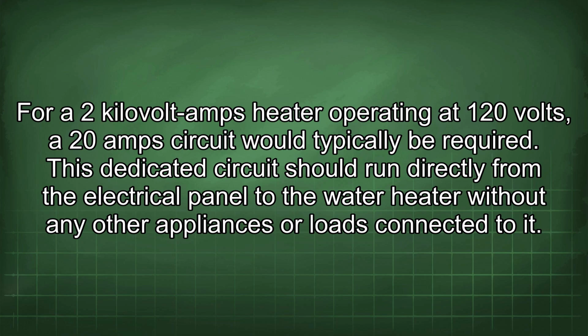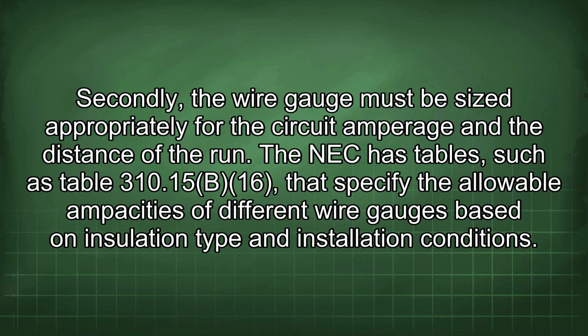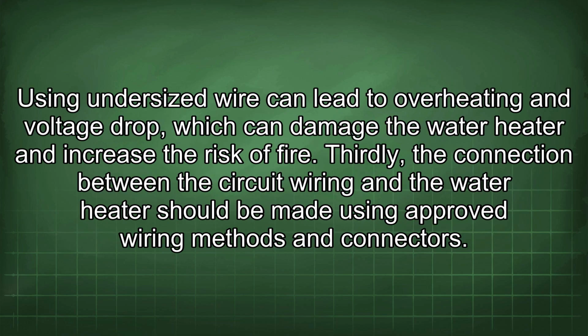Secondly, the wire gauge must be sized appropriately for the circuit amperage and the distance of the run. The NEC has tables, such as Table 310.15(B)(16), that specify the allowable ampacities of different wire gauges based on insulation type and installation conditions.